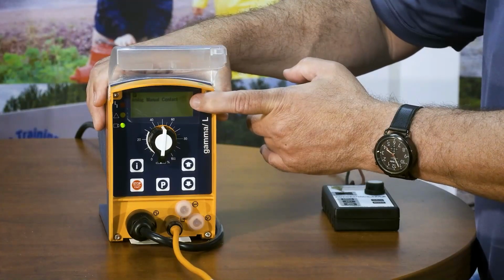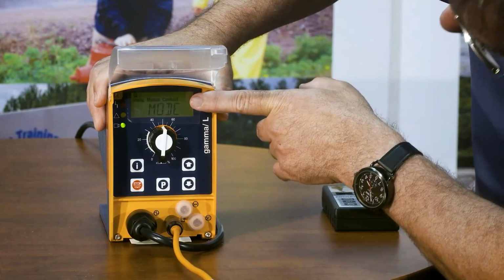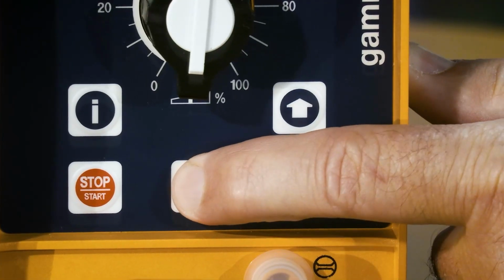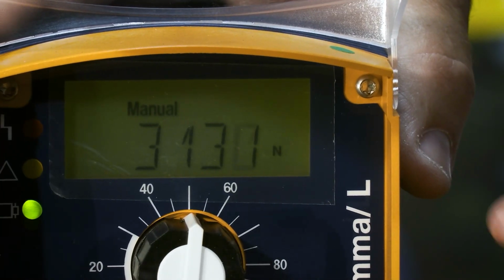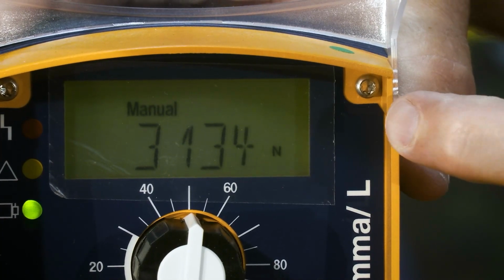Many chemical feed pumps can be programmed to operate flow proportionally, whereby the amount of chlorine solution injected is controlled by the flow of the water to the distribution system. This is a flow-paced system where the metering pump works in communication with a flow meter and adjusts based on water demand. They can also work manually or independently of a flow meter. In manual mode, the chlorine solution is injected at a set rate regardless of water demand.